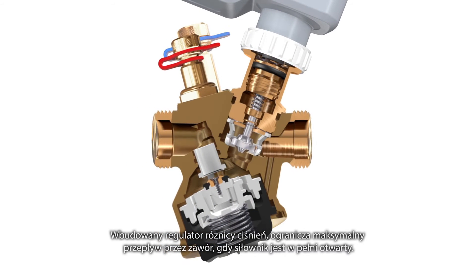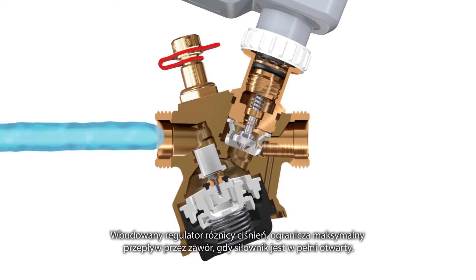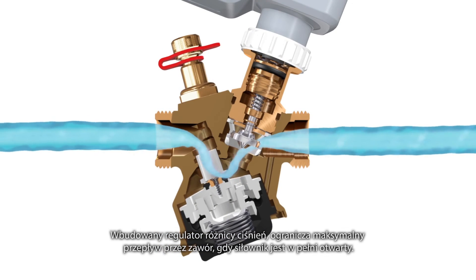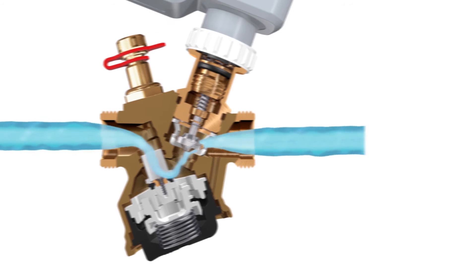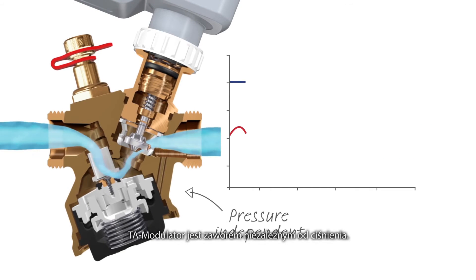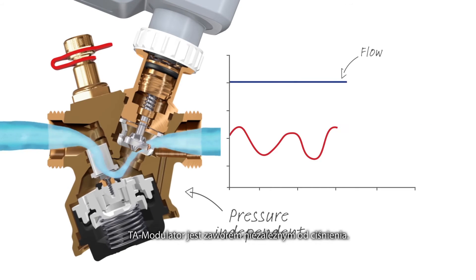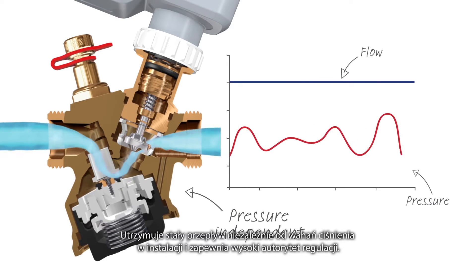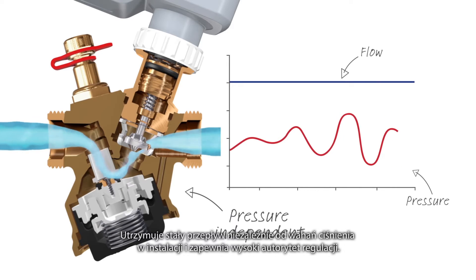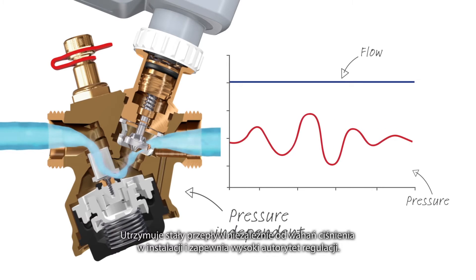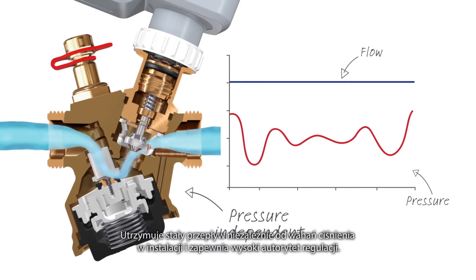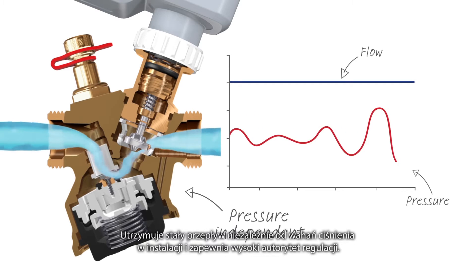The built-in pressure controller limits the maximal flow through the valve when the actuator is fully open. TA Modulator is a pressure-independent valve — it keeps the flow constant regardless of pressure fluctuations in the system and guarantees high control authority.